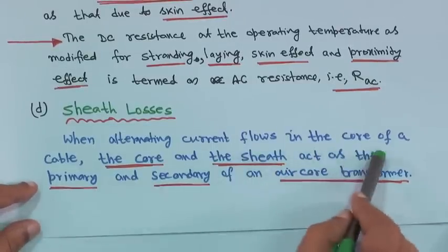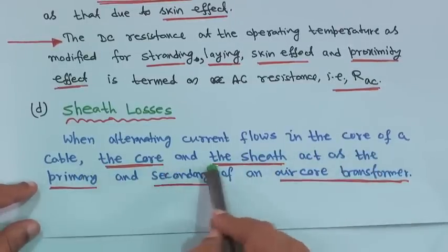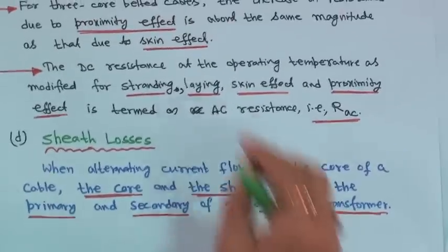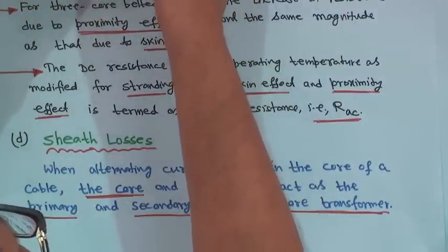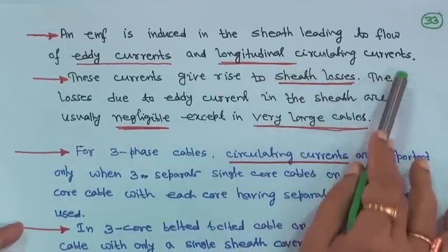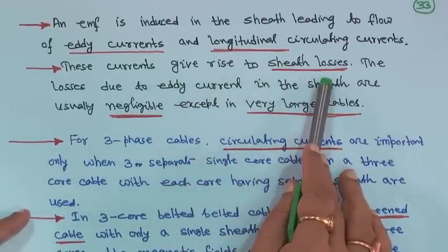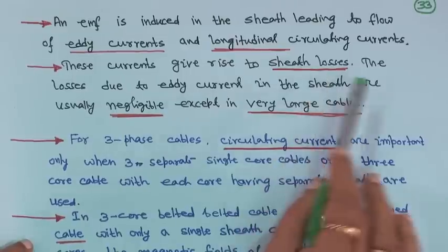When alternating current flows in the core of a cable, the core and the sheath act as the primary and secondary of an air core transformer. Therefore, an EMF is induced in the sheath, leading to flow of eddy currents and longitudinal circulating currents, and these currents give rise to sheath losses — there will be some power loss in the sheath.